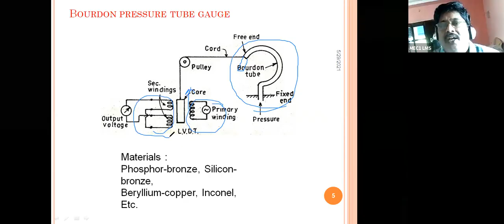When the bourdon tube expands, we arrange it with the help of a pulley, so when it moves in this direction as the bourdon tube expands, the core will move upwards. We can send pressurized fluid so it expands, and thereby the LVDT core moves top to bottom. This is the primary winding and these are the two secondary windings connected in series, as we already discussed for the linear variable displacement transducer, or linear variable differential transformer.